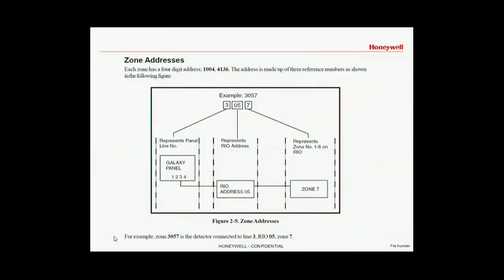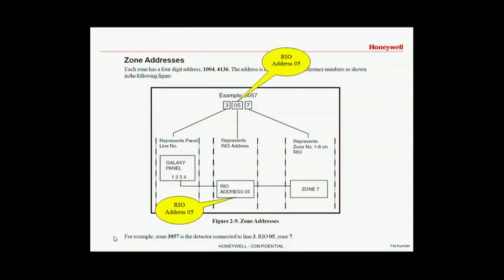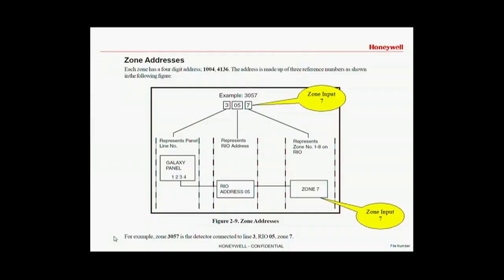When we look at individual zone addresses, the first digit will always be referenced to the dataline connected to the panel. The next two digits will be the module address — in this case it's 5, so it becomes 05. The final digit will be a zone number between 1 and 8, or alternatively if it's an output it will be between 1 and 4.